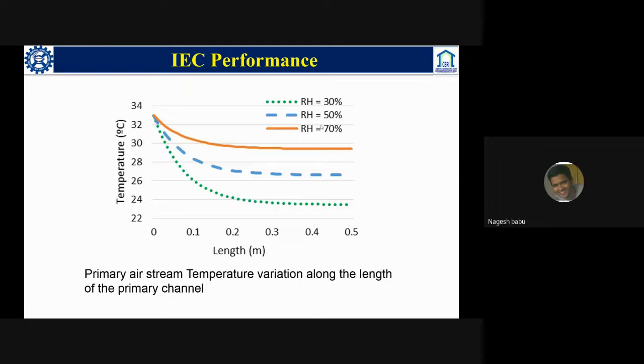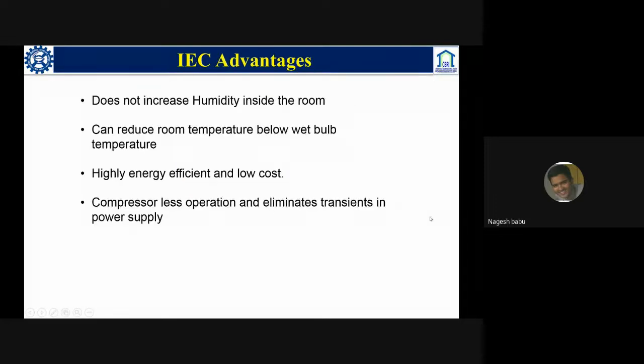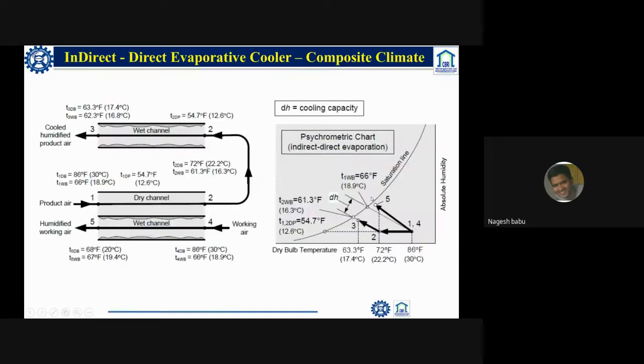If there is 30% relative humidity air, it has the scope of reducing the temperature even up to 22 degrees centigrade, because its wet bulb temperature decreases. So the advantages of IEC: it does not increase the humidity inside the room, it can reduce room temperature below wet bulb temperature, it is highly energy efficient and low cost, it has compressorless operation, and it eliminates transients in power supplies. So now, in the indirect evaporative cooling, we have reduced the temperature up to 22 degrees centigrade.